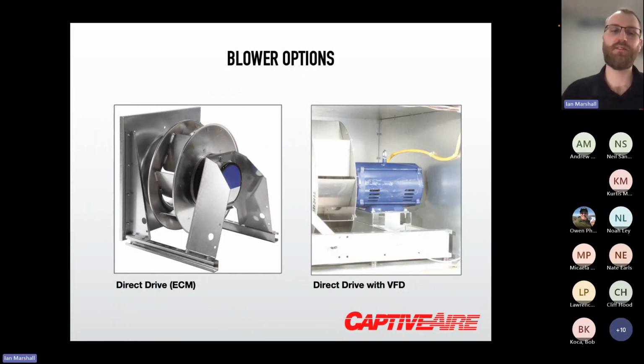For our blower options, again, no belt-driven motors in the unit. It's all direct drive fans. So we have an ECM fan standard, or ECM or a direct drive with VFD. Typically, we'll standardize with the direct drive with VFD, but it kind of depends on the static and the airflow of a given cabinet size based on what we'll select.